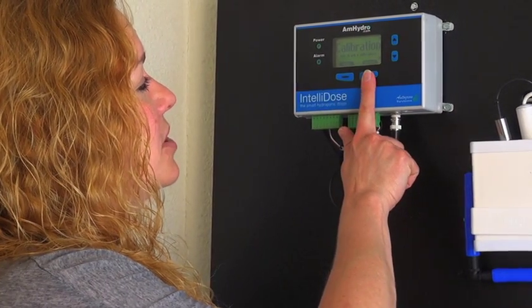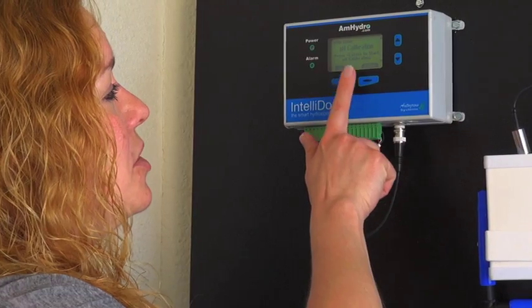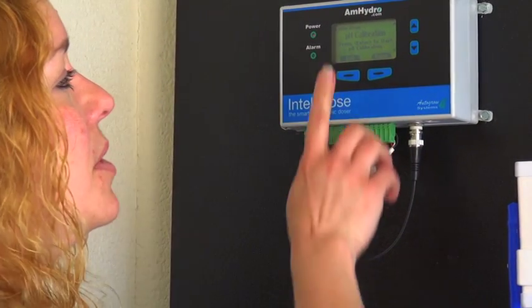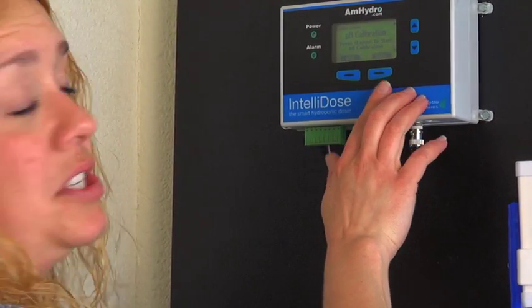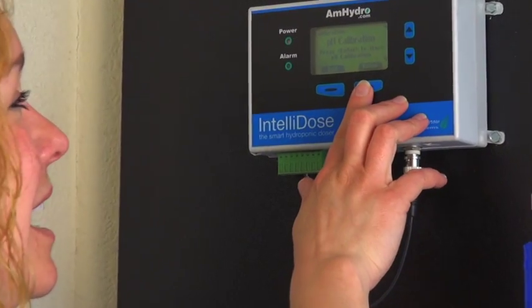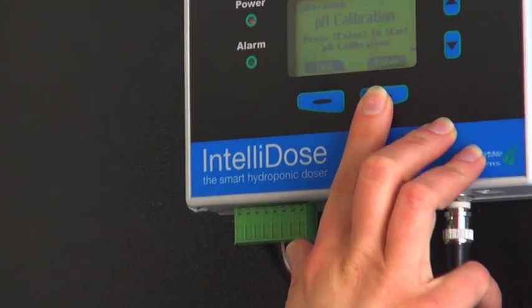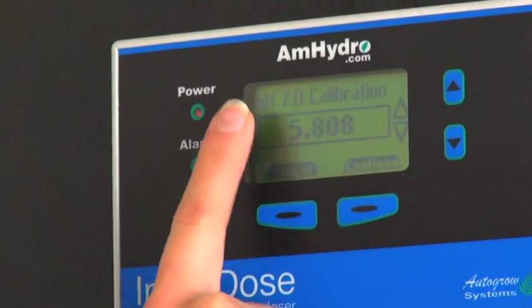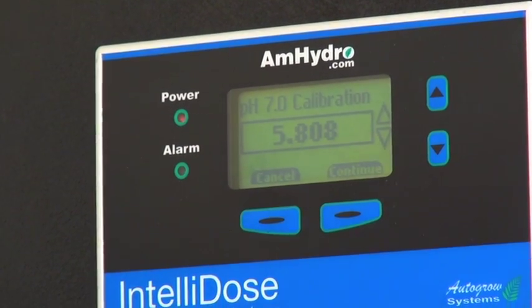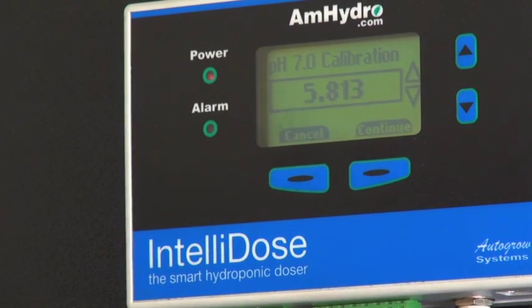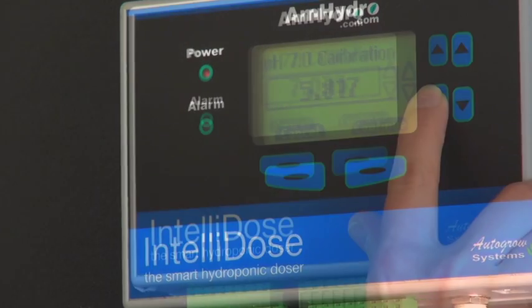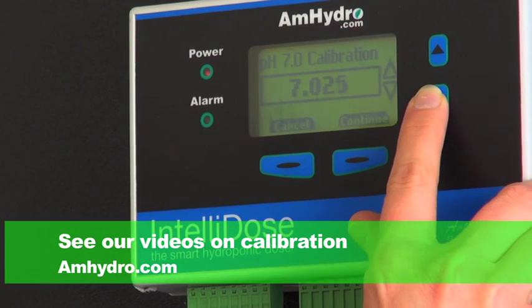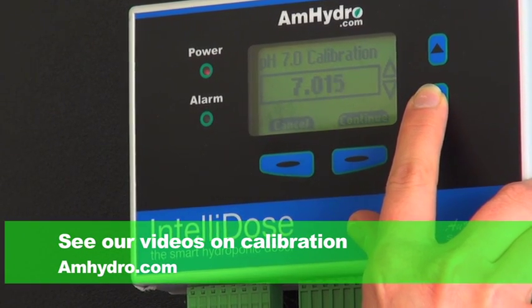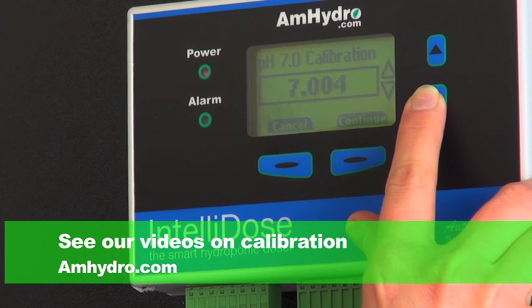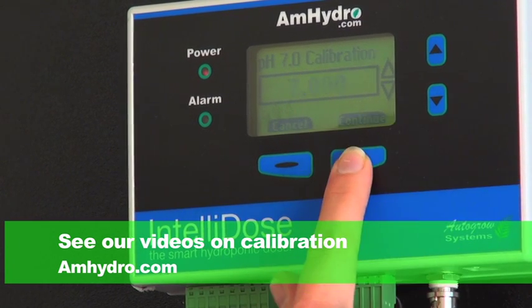When you enter into the inner screen, it's going to tell you that you want to do pH calibration first. So it'll say press enter to start pH calibration. The IntelliDose is very informative, explains to you what you need to do. So you hit enter and it'll say pH 7.0 calibration. At this point you will have your pH probe and you'll put it into your 7 solution. Once you've let it temperature compensate, which is usually 3 to 4 minutes, you use your arrows to dial it into 7.0 and you hit continue.